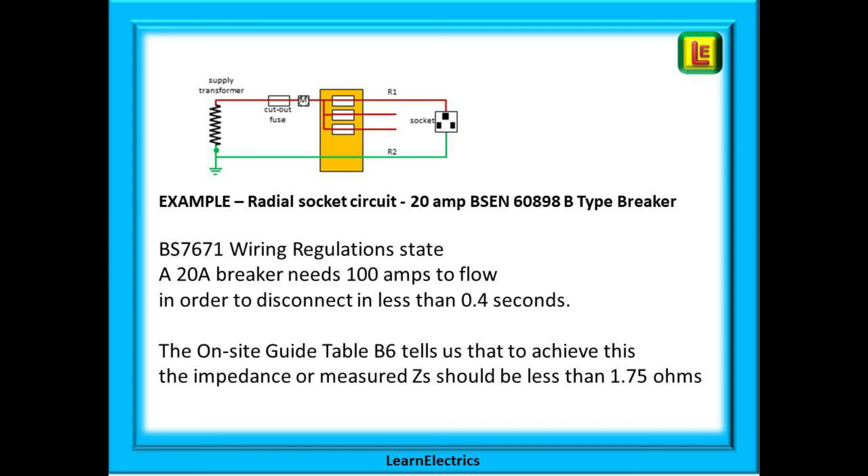We cannot easily measure currents in the circuits, but we can measure resistances and impedances with our meter, and then we can use Ohm's law to calculate the current that may flow. Fortunately, there are standard tables in the onsite guide with everything already worked out for us. They tell us what the maximum resistance of a circuit should be in order that the required minimum current will flow. In this example for a 20 amp B type breaker, the tables will tell us the maximum resistance permissible in order to achieve the required fault current of at least 100 amps. And consulting table B6 of the onsite guide, the electrician will find a value of 1.75 ohms maximum is shown.